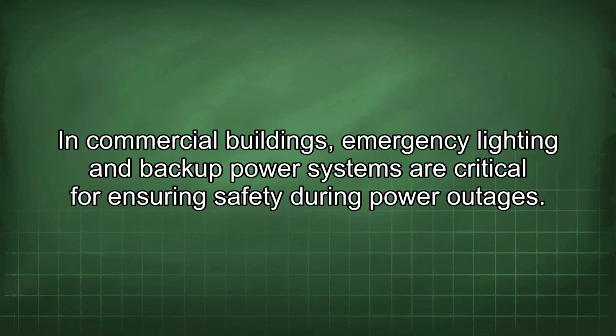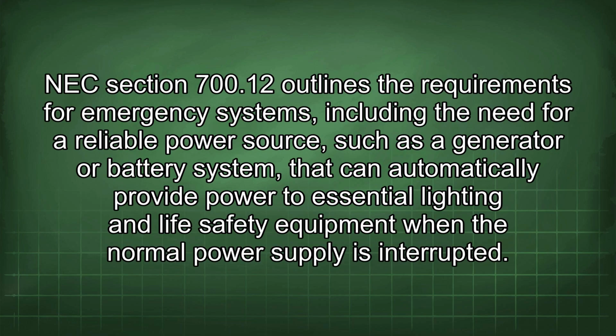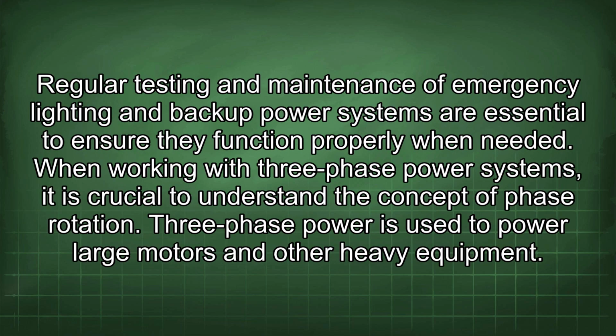In commercial buildings, emergency lighting and backup power systems are critical for ensuring safety during power outages. NEC Section 700.12 outlines the requirements for emergency systems, including the need for a reliable power source, such as a generator or battery system, that can automatically provide power to essential lighting and life safety equipment when the normal power supply is interrupted. Regular testing and maintenance of emergency lighting and backup power systems are essential to ensure they function properly when needed.